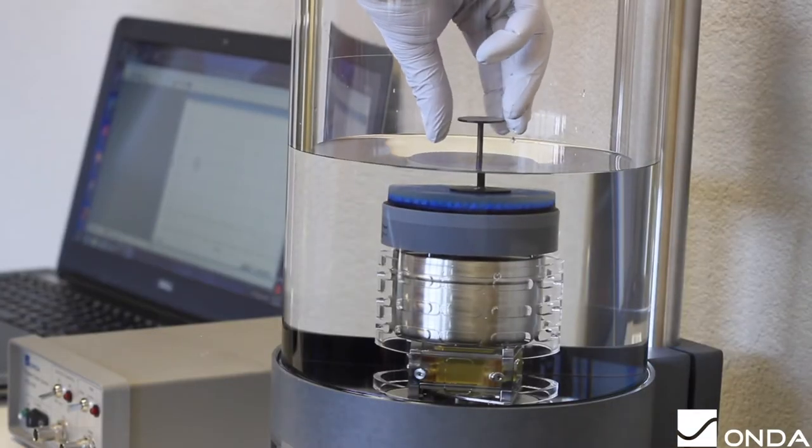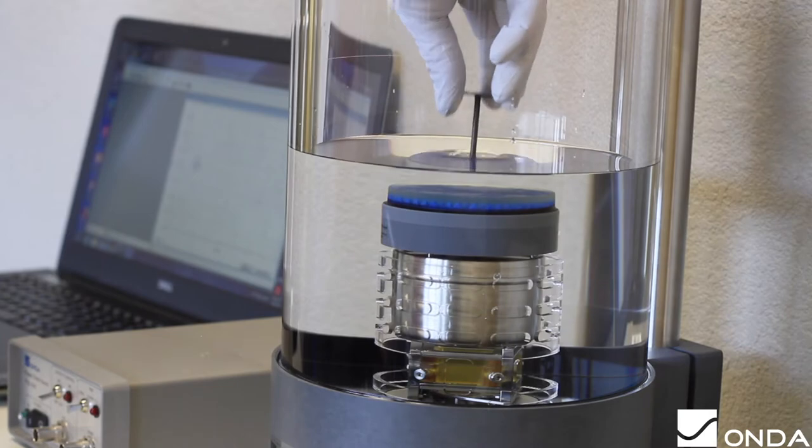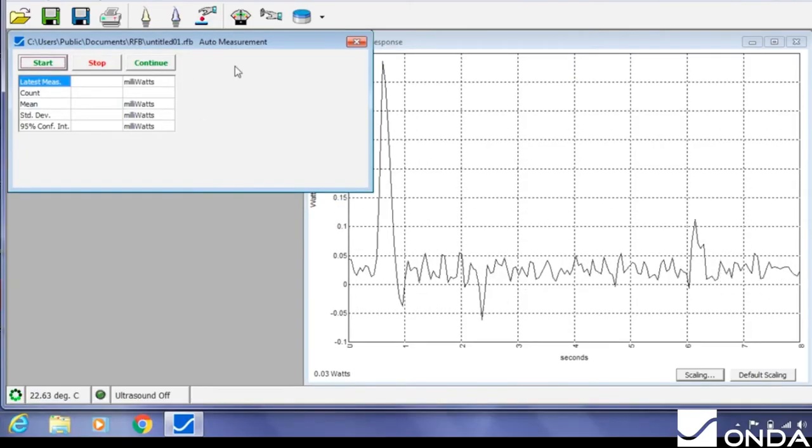When running the mass cal, make sure to remove the stand and re-zero the system before exiting the calibration routine.